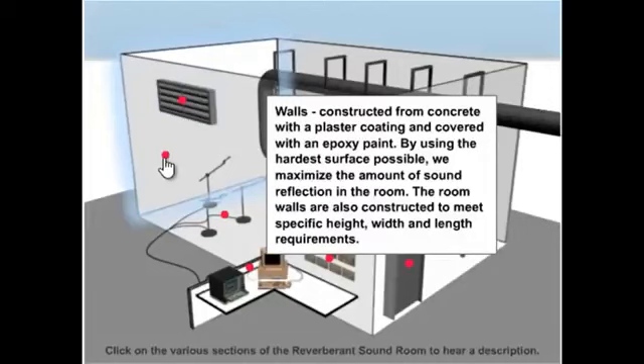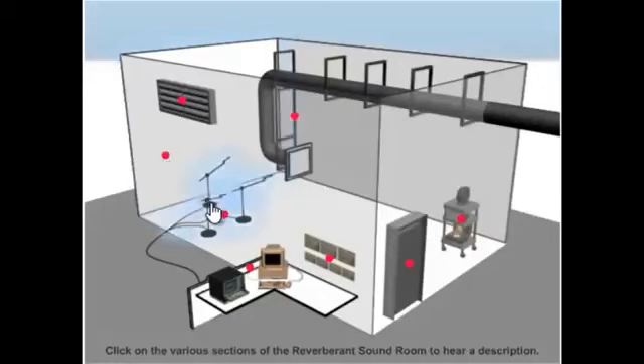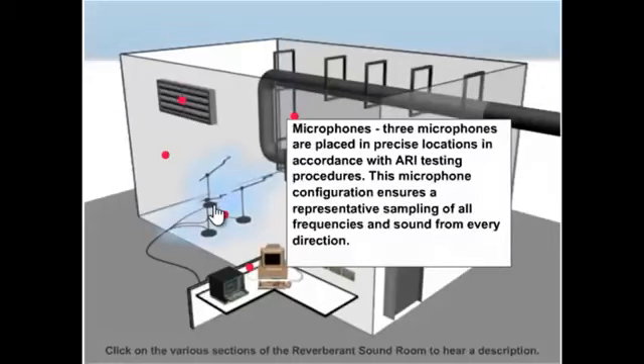Walls are constructed from concrete with a plaster coating and covered with an epoxy paint. By using the hardest surface possible, we maximize the amount of sound reflection in the room. The room walls are also constructed to meet specific height, width, and length requirements. Microphones. Three microphones are placed in precise locations in accordance with ARI testing procedures. The microphone configuration ensures a representative sampling of all frequencies and sound from every direction.